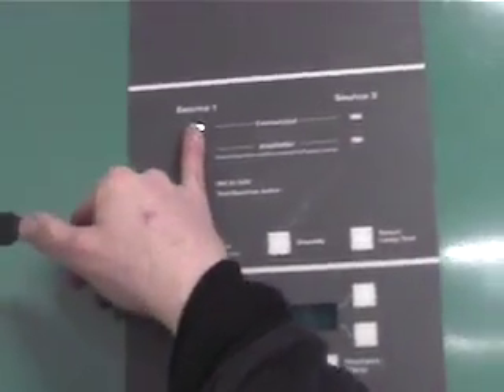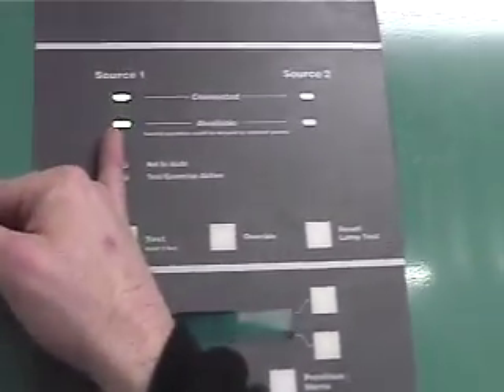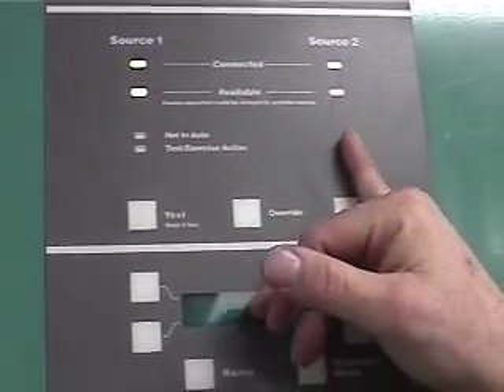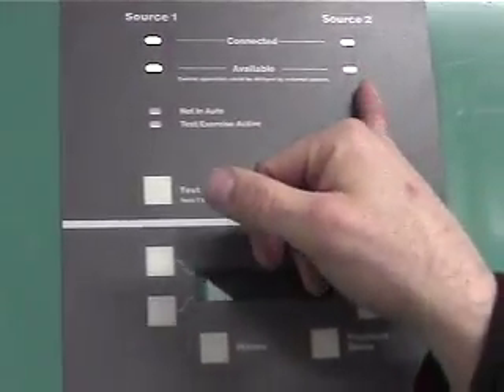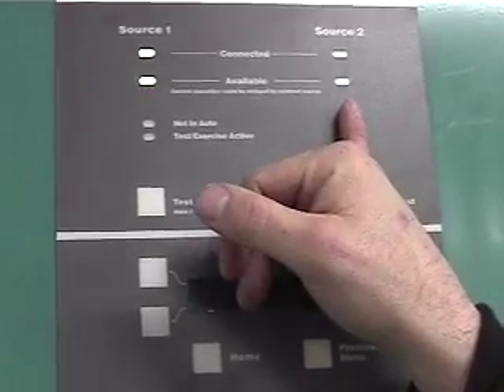Your source 1 is our normal utility power. Source 2 is the generator. We can have the generator available right now, but we can only be connected to one source or the other. We'll never be connected to both sources at the same time. That's a bad thing.